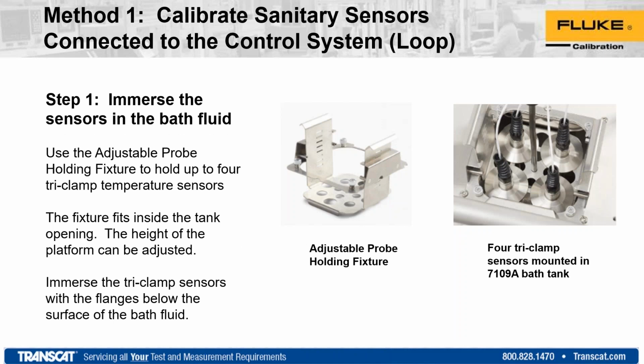So to set this up, these are some of the new features we've come up with for the bath. There's an internal holding fixture, and what this allows you to do, depending upon size, is adjust the depth. If you look at the picture on the right, you can actually get 4 sensors in the tank with a reference probe if needed. And those flanges on that one, I believe, are 2-inch round. So you can get quite a few more versus one at a time. So if downtime is a concern, this is a really good setup.